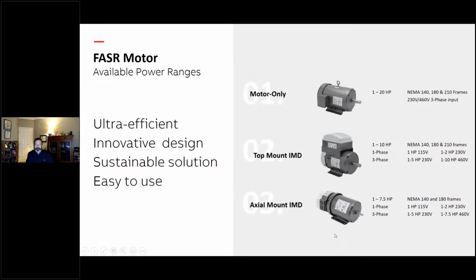The design is available now basically up to 20 horsepower as a motor only. And again, like I said, that's where the need in the market is, that lower horsepower where a traditional permanent magnet motor is too expensive. And then there's a lot of initiative where we don't want to mount the drive in a control cabinet. We'd rather have it right on the motor. So you'll also see a lot of trending, like an electrically commutated motor has the drive built into it. There's a lot of requesting for that in fan systems and pump systems, especially if you're changing out an old induction motor and you don't want to worry about where you're going to put this drive, and how you're going to find cabinet space to put it. So there's a lot of need to have the drive mounted on the motor, either on the back end or on the top of it.